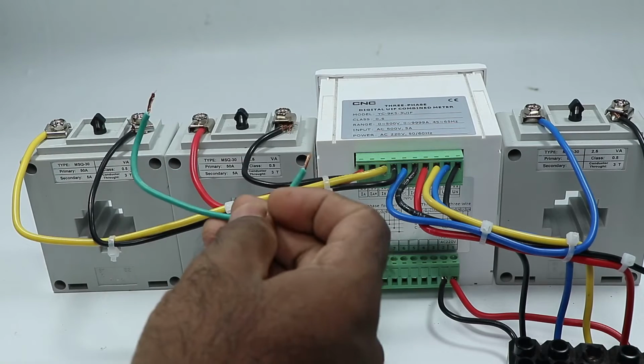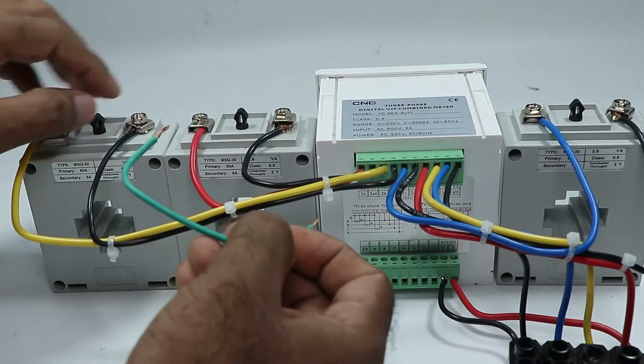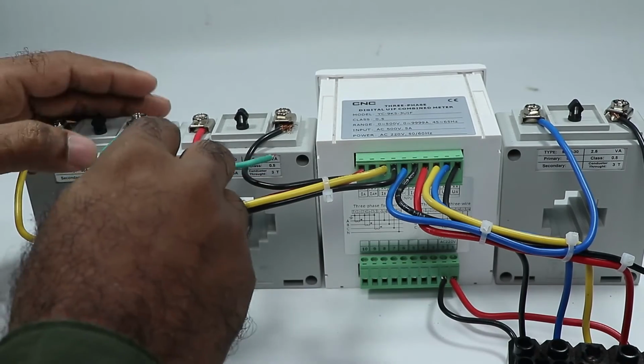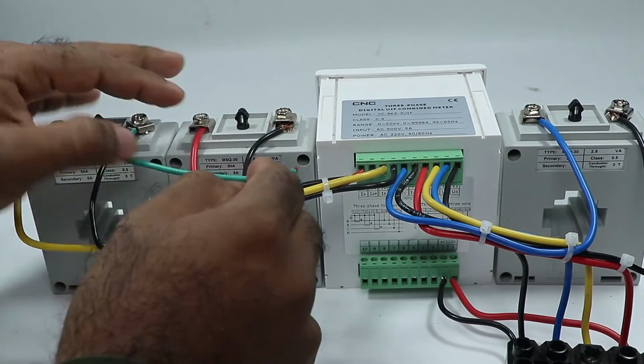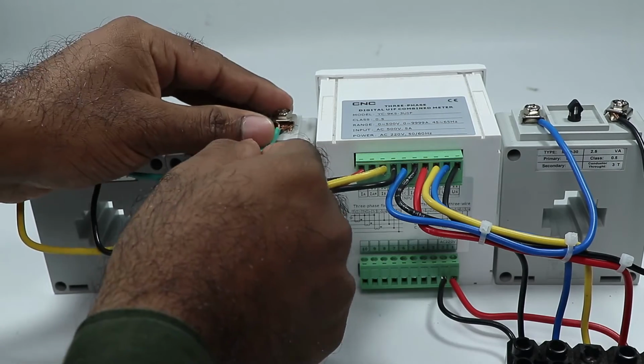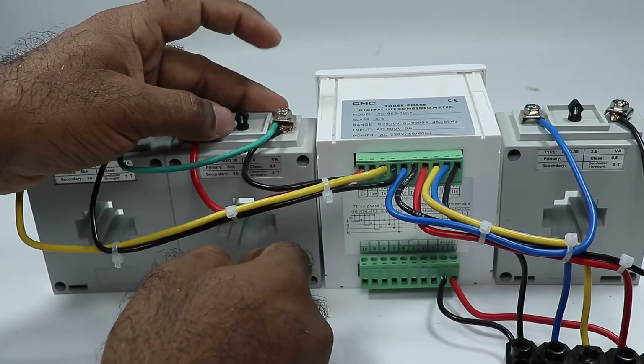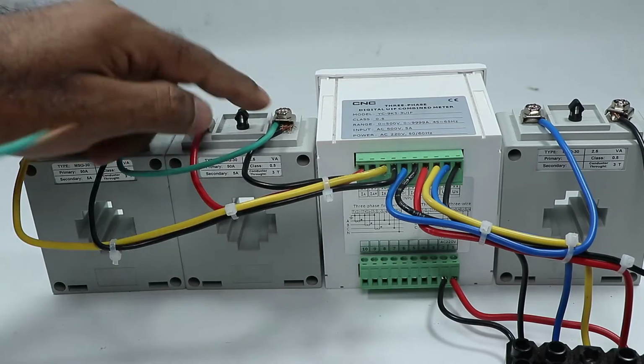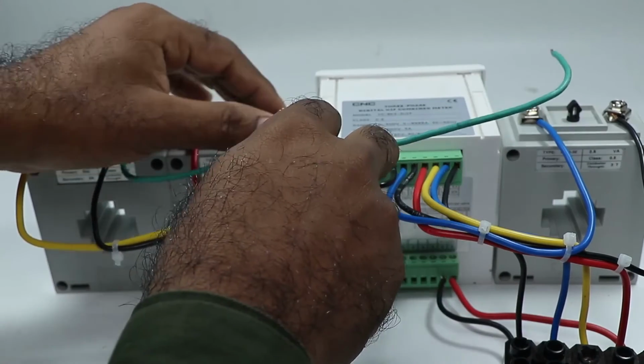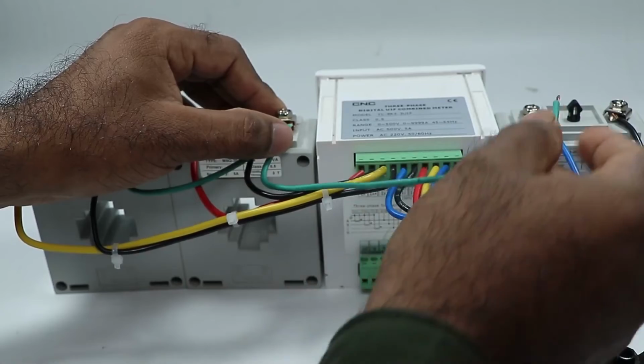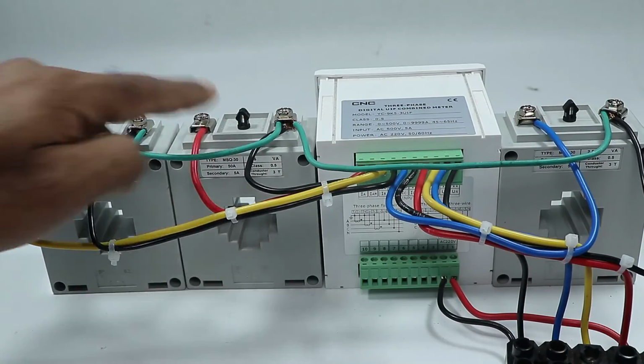Take this piece of wire. At this CT's S2 terminal, connect this wire. Take the other end of the wire and connect it at the S2 terminal of another CT. Similarly at this terminal connect one more wire. The power supply from this wire will go to another CT's S2 terminal. So in all these CTs, all the S2 terminals are being shorted.